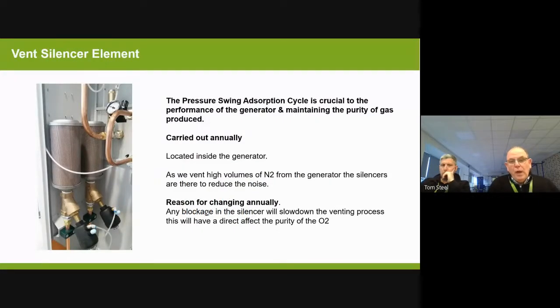Now, a simple thing, guys. You're going to replace the silencers on a yearly basis. Now, the silencers are not just there to reduce noise. Yes, that is their primary function, to reduce the noise. So why do we have to change them? Silencers can get blocked. What happens in the PSA system? You see we have two large silencers there, one for each bank of columns.